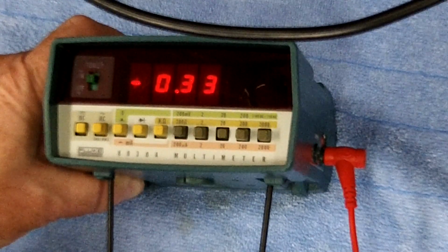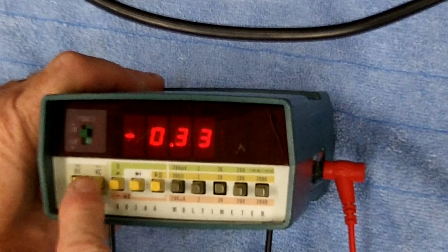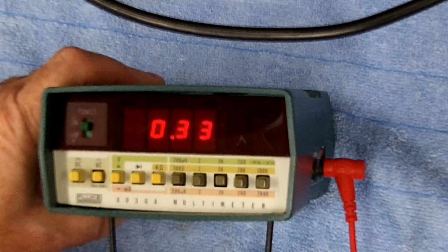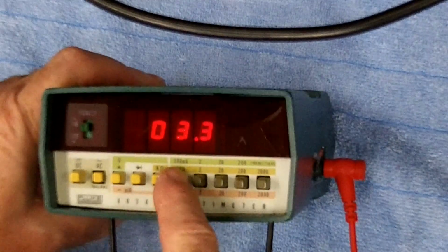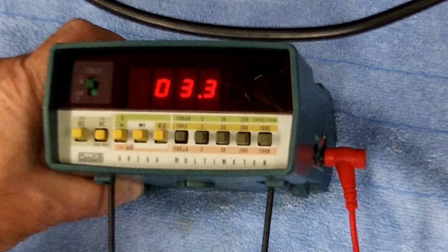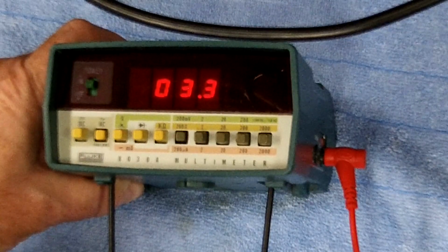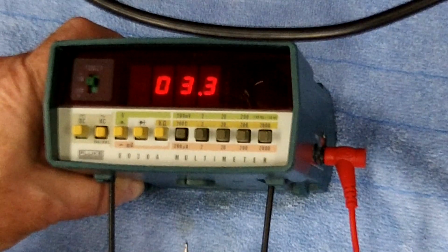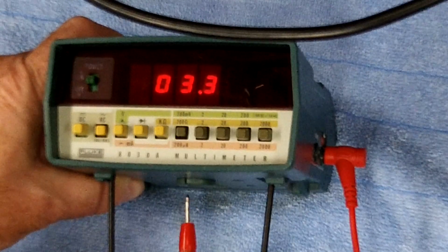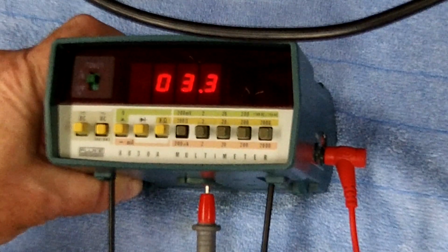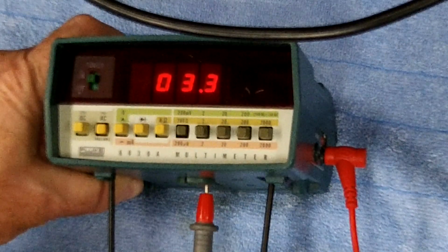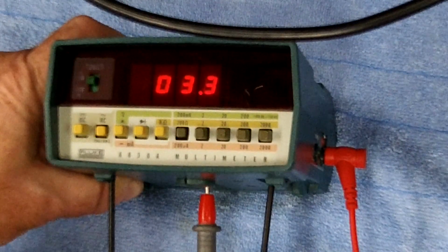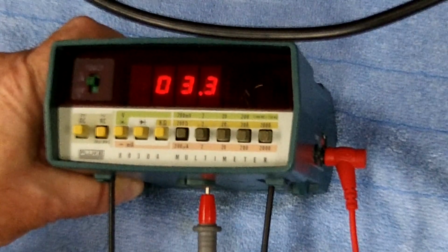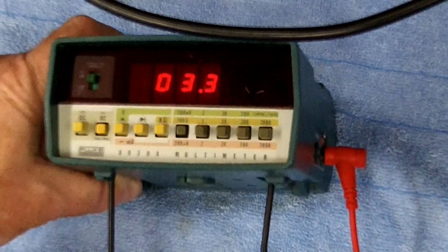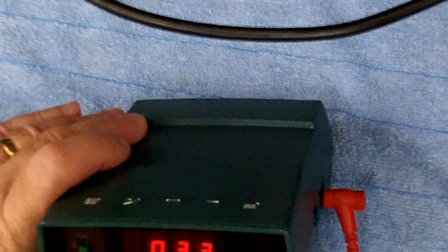Check the AC volts. Select the volts AC in the 200 millivolt range. So here's AC, 200 millivolts. This voltage will be as much as 60 millivolts battery operation or 130 with the battery charger power eliminator's power source. And again, we got nothing. Hasn't changed. Okay. Let me set that down for a second so I can roll up to the next page.